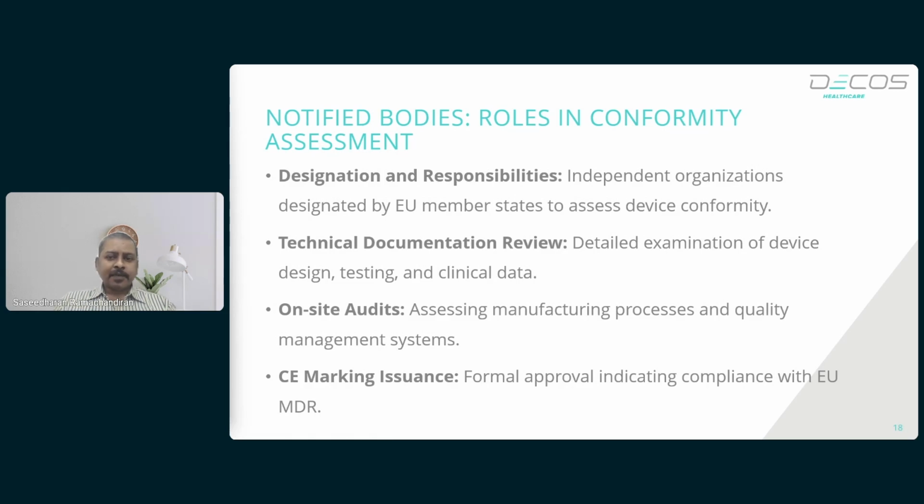Continuing with the topic of assessments, let's discuss the role that a notified body plays in the EU MDR conformity process. Notified bodies are independent organizations designated by the EU member states to assess whether medical devices meet the MDR's requirements. Notified bodies play a very key role in technical documentation review, where the notified body examines the manufacturer's technical files to ensure compliance. They conduct facility audits to evaluate the quality management system. Once compliance is confirmed, the CE mark is issued, allowing the device to be sold in the European Union.